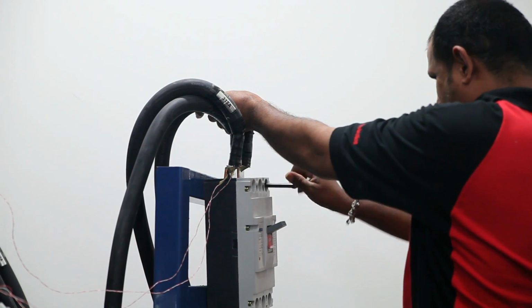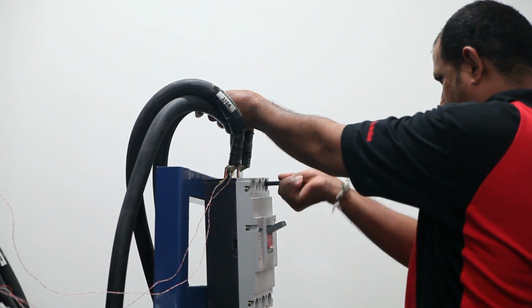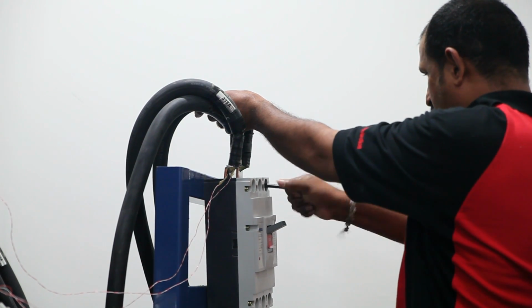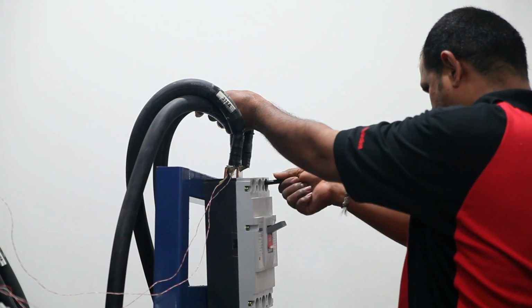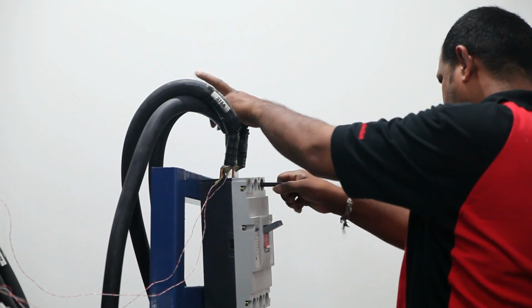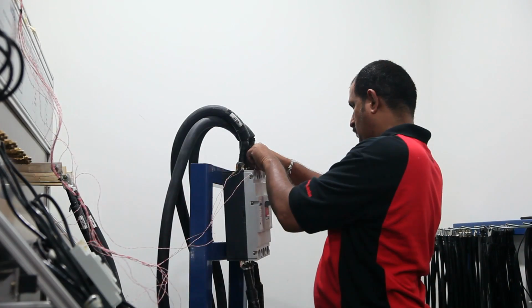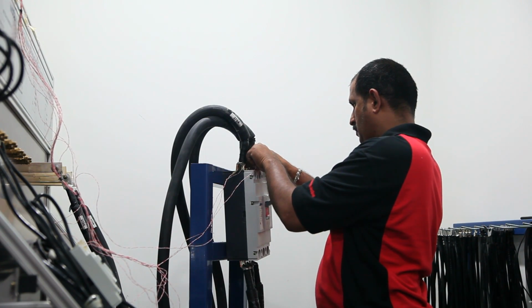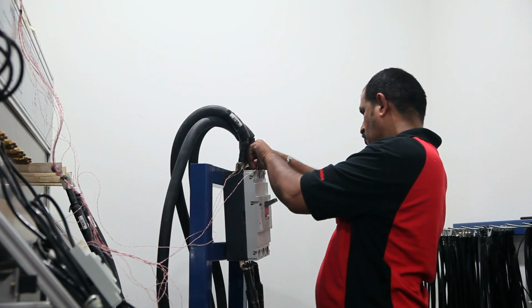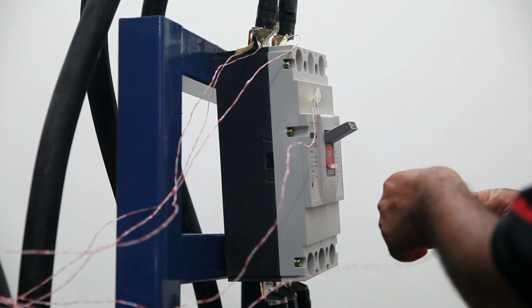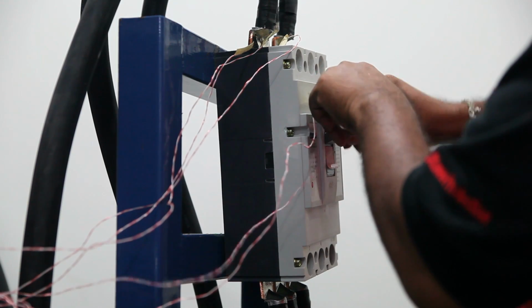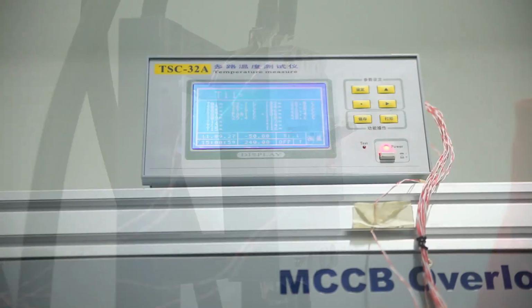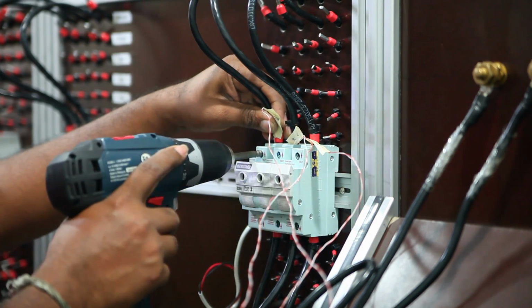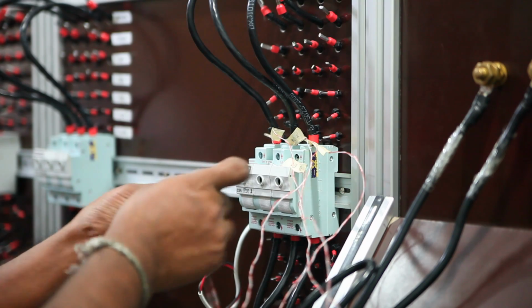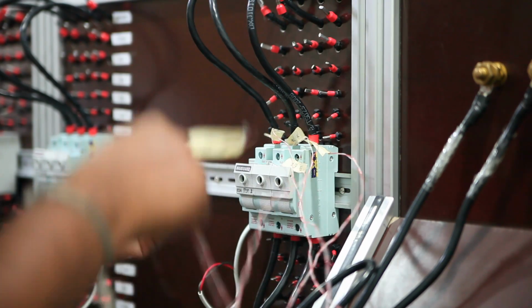Temperature rise limit test. The temperature rise limit test is very important to verify the capability of electrical switchgears and wiring accessories to withstand thermal stress at elevated temperatures within the set limits. The test equipment is fabricated to adapt to performing tests for MCBs, MCCBs, RCCBs, isolators, and switch fuses. Ambient conditioning is made possible with an enclosed control room. The correct current is preset and programmed.